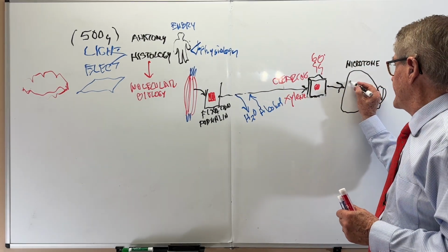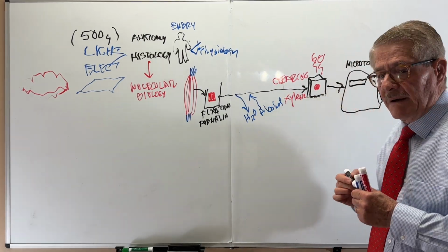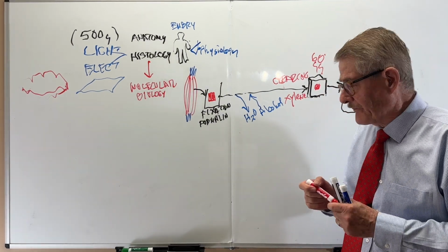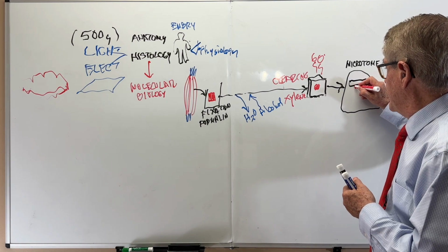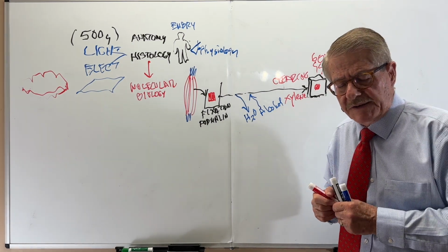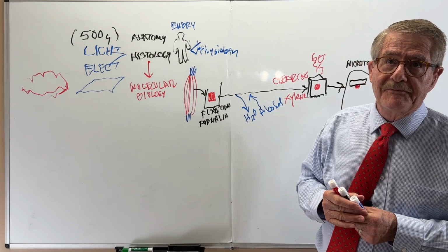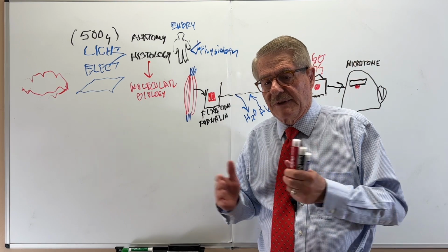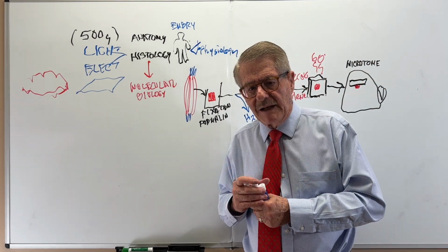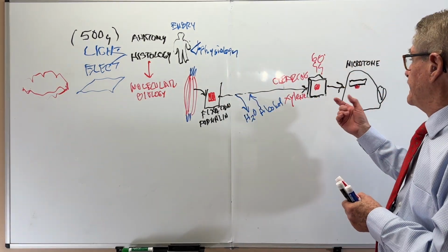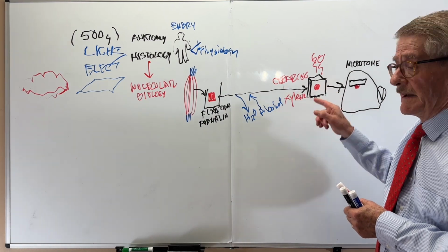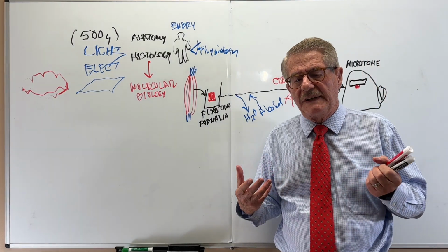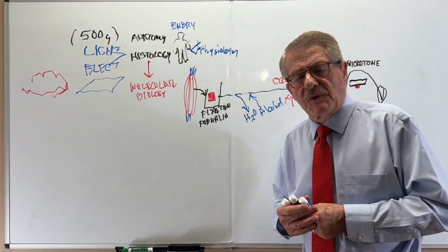The blade is located in the upper portion or lower, depending on the instrument. And the tissue and the paraffin is going to be here, and you're going to get sections that are very thin. How thin? About less than 10 microns, 5 microns, 3 microns, depending mostly on the embedding medium. If you have a plastic embedding medium, you are going to get thinner sections and a luxury of details, which may be very useful for certain materials.